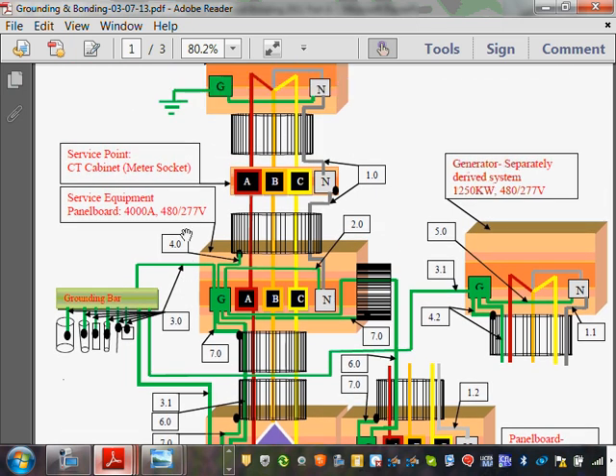Can you guys see that? Here's my enclosure, here's my system. Both of them have their own grounding electrode system. Now I need to tie the two together. How do you tie them together? Through the main bonding jumper. Through the neutral, can you guys see the neutral? Bringing it here, tying it to the switchgear. You take your neutral and you tie it, so you're tying the grounding electrode system of the utility to the grounding electrode system that you own and operate and create, through something called the main bonding jumper.